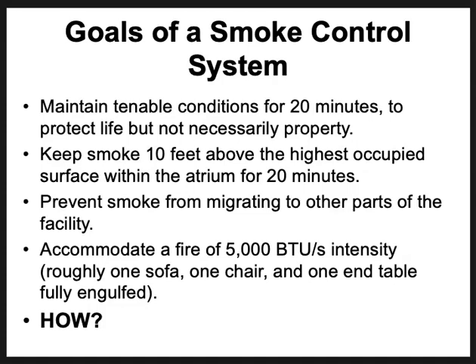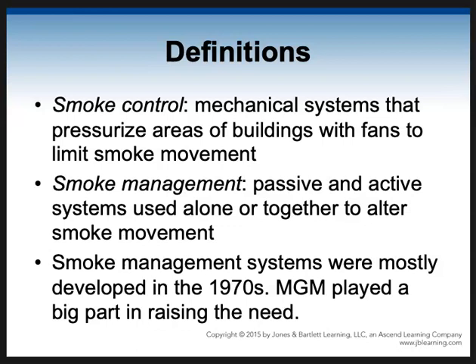So how are we going to do that? How are we going to provide that tenable environment and keep the smoke from banking down? Well, there's three basic ways we're going to do it, but we talk about smoke control and smoke management, okay? So smoke control is the mechanical systems that pressurize areas of buildings with fans to limit smoke movement. Smoke management, with that, we're talking more about the passive and active systems used alone or together to alter the smoke movement. So smoke management systems were mostly developed in the 70s, and again, that MGM fire played a big part in raising the need, and some other fires that happened around that time.